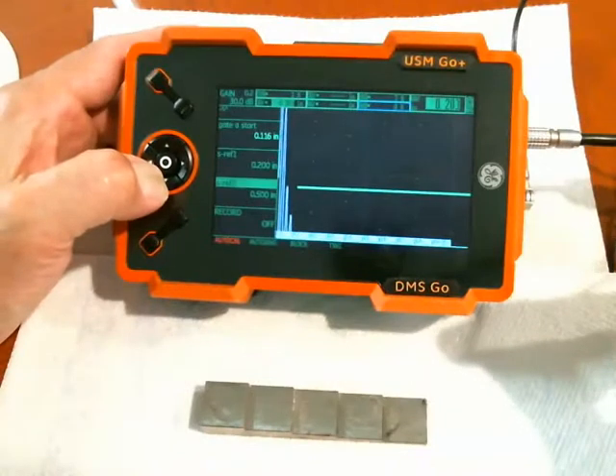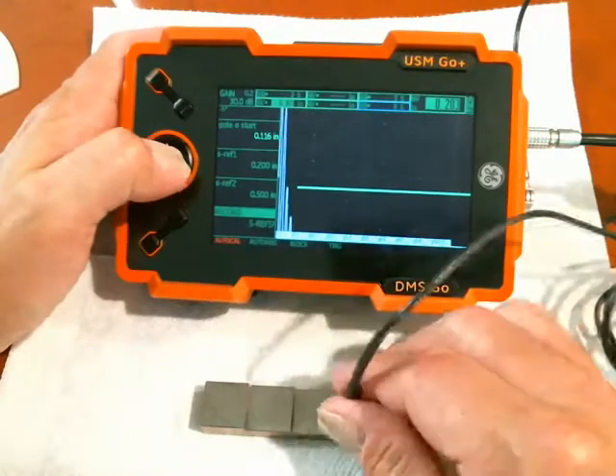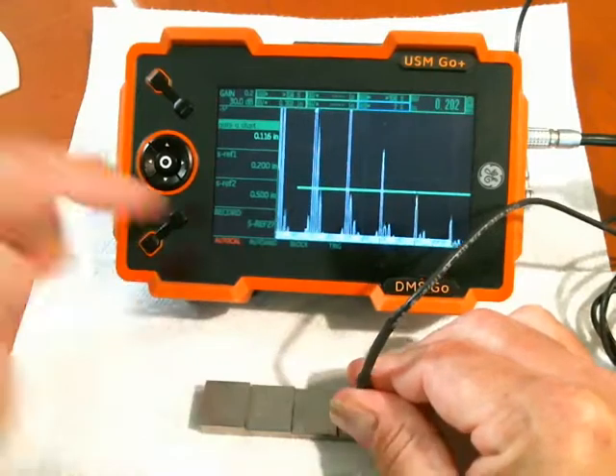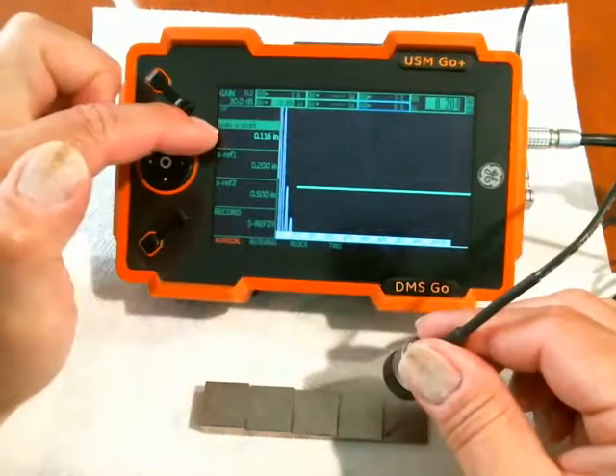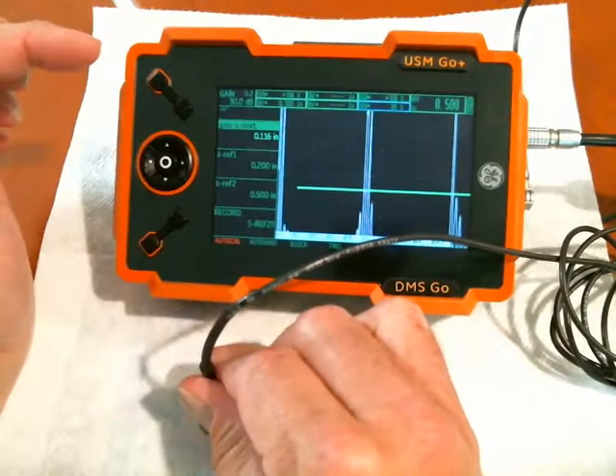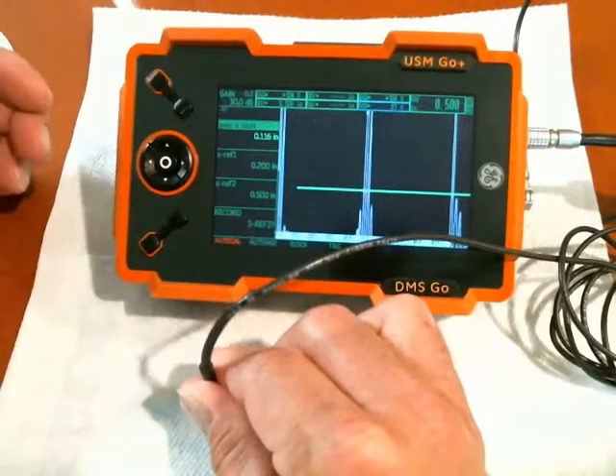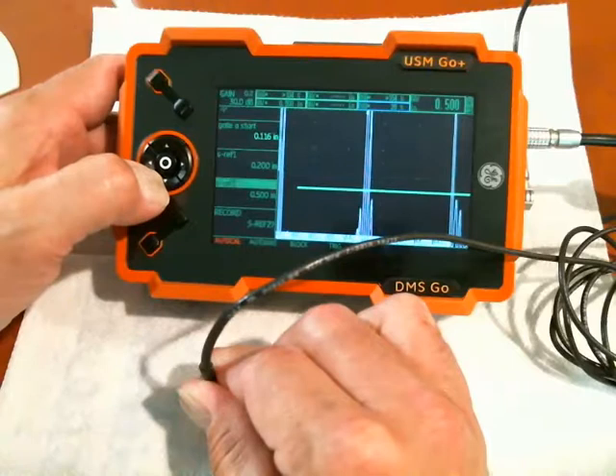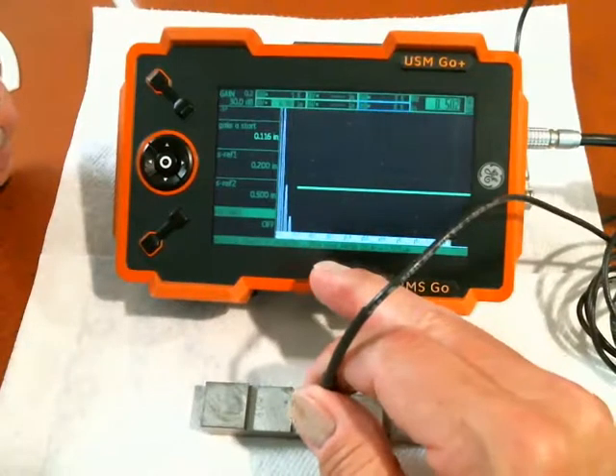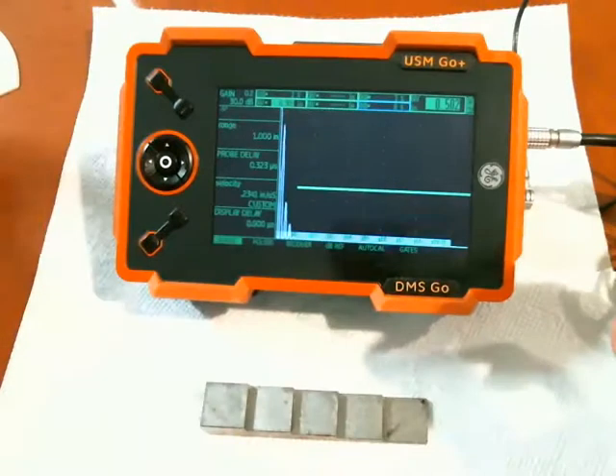If I go down in this menu to record and click right, it says sref1, so I put it on the thin step and click right. Now it's saying sref2, and it popped back up to the top of the menu so that if I needed to move my gate to pick up the 0.5 inch step, I'm already positioned to easily move the gate. In this case I don't need to move it — there's nothing to interfere. So I come back down to record, I'm on my half inch block, I go right again. It says auto cal complete: 0.2341 inches per microsecond. And it told me what the probe delay was too.